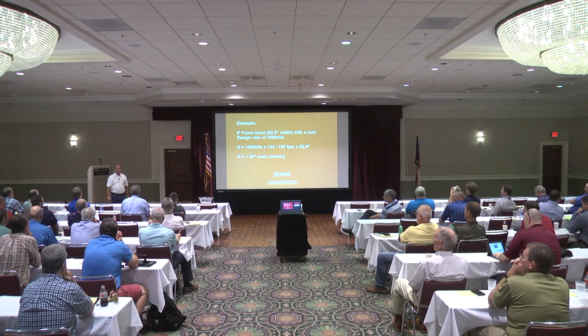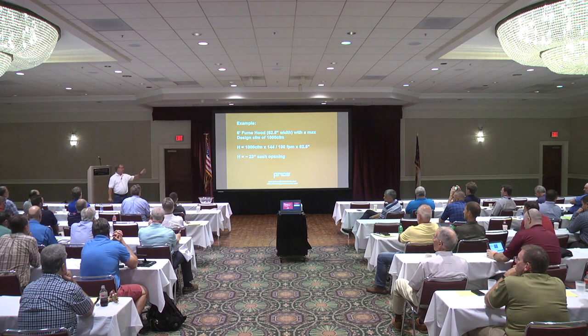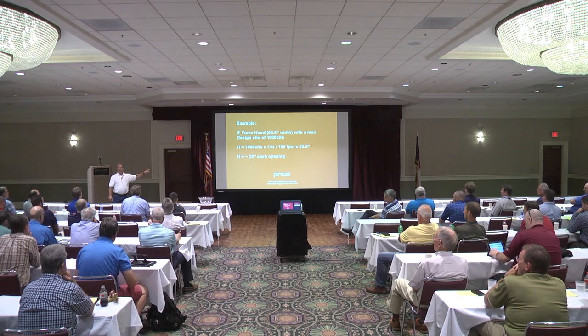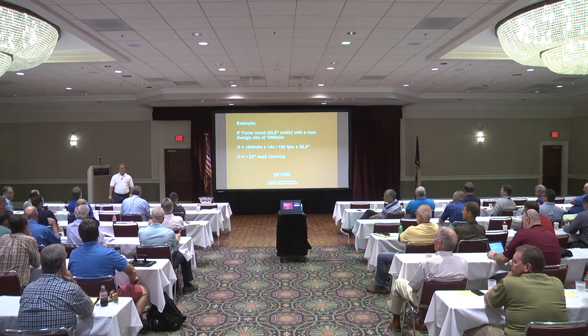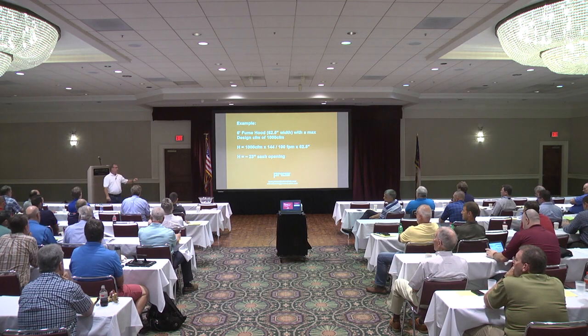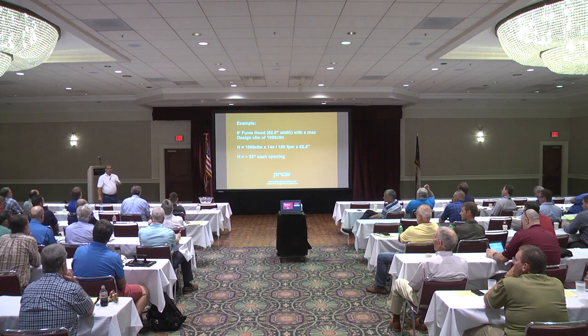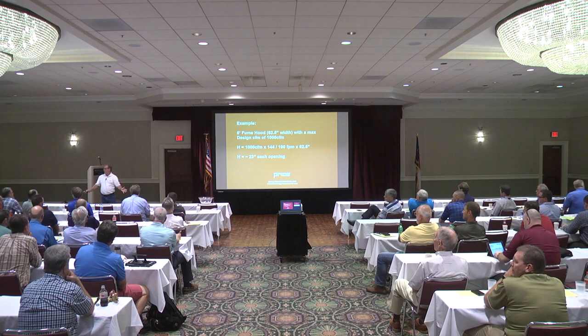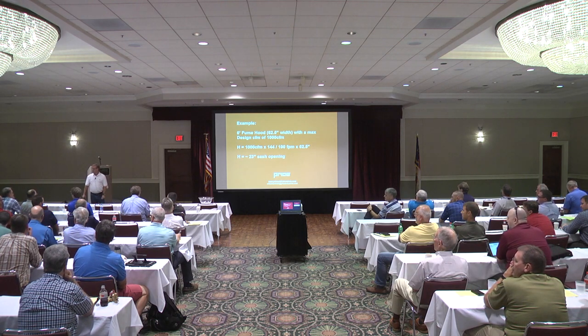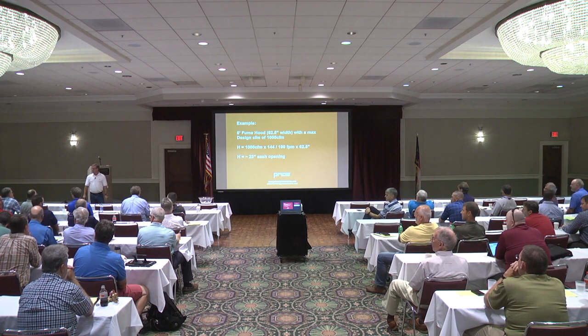That's a pretty standard velocity for a fume hood. If it was 80, plug 80 in there. If it was 110, plug 110 in there. Exactly. So I think we all agree 100 feet per minute is a pretty standard fume hood design point. So is 18 inches. So 100 feet per minute at 23 tells me the same thing as 18 inches, and I'm running 127 feet per minute.